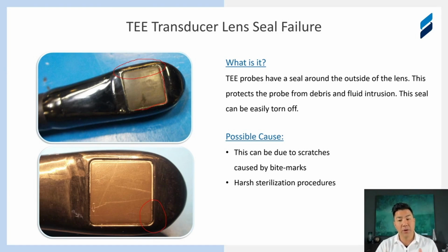If it's over a longer period of time and it's not caught, what happens is that the materials of the crystal just break down. There's nothing to repair anymore. It literally just disintegrates. So the earlier you can catch these failures, the longer life you're going to be able to have with these probes by catching it early, getting it repaired, and a repair price is far less expensive than a full replacement if you leave it too long.